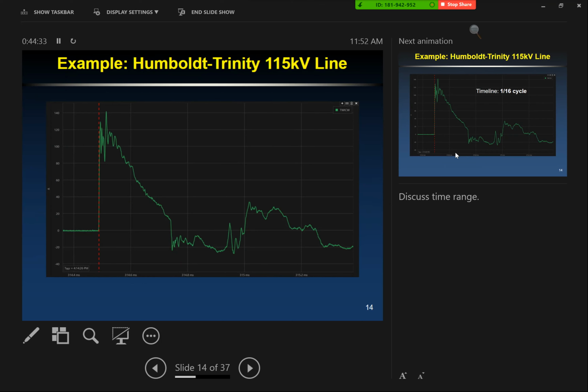You have ringing on the CT, and sometimes that shows up at the very beginning when you have this first impulse. This is the traveling wave that arrived from the fault. You get all this ringing showing up, bounces along the CT lead lengths. So it just takes some time to kind of try to put this together.